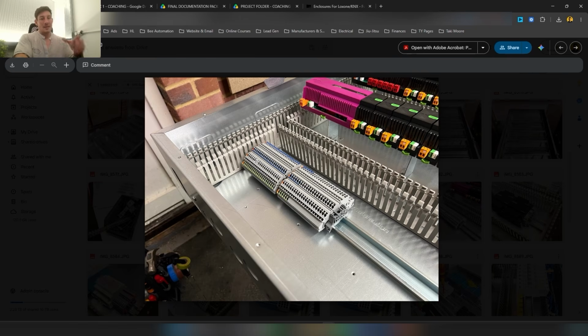So we're just getting all the terminal blocks in place from our terminal block layout. I'd always recommend designing your terminal blocks prior, rather than trying to do it on the fly whilst wiring. It's so much easier to put your mental energy in during the design phase, in a computer office environment where you're locked in thinking about all of this, rather than trying to think it through at the panel build phase. It's so much nicer at the build phase to go full steam ahead with the wiring - you might change the odd thing here and there, but you've already thought it through. So this is going in place, referencing the terminal block layouts you should get access to in the resources, just making sure they're all in place.